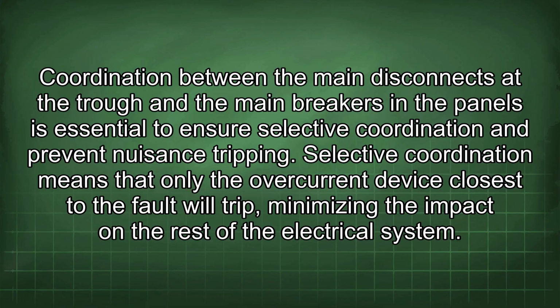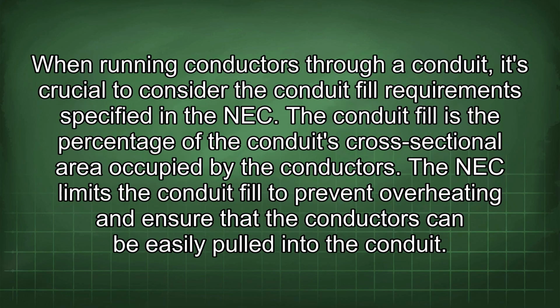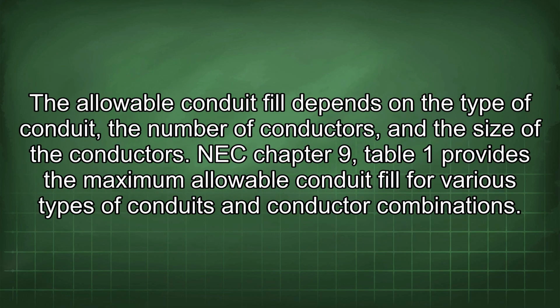When running conductors through a conduit, it's crucial to consider the conduit fill requirements specified in the NEC. The conduit fill is the percentage of the conduit's cross-sectional area occupied by the conductors. The NEC limits the conduit fill to prevent overheating and ensure that the conductors can be easily pulled into the conduit. The allowable conduit fill depends on the type of conduit, the number of conductors, and the size of the conductors. NEC Chapter 9, Table 1 provides the maximum allowable conduit fill for various types of conduits and conductor combinations.